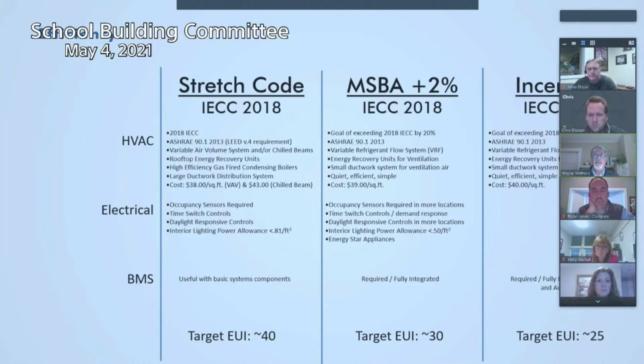We've been using boilers, and we've gone to high efficiency condensing gas-fired boilers, achieving efficiencies in the mid-to-upper 90s. We've gone from unit ventilators, which had their share of problems and were noisy, to VAV systems, which provide very good system control, acoustics, and thermal control. Then advancing to chilled beams, where the air going through a chilled beam is really primarily the ventilation air that becomes the motive force for the whole HVAC system - at that point you're moving smaller quantities of air.